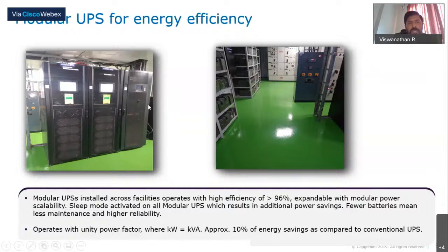Likewise, we have gone for a modular design so that we do not waste space. At the same time, these UPS are highly energy efficient and we could save 10% of the energy compared to a conventional UPS. This UPS gives almost 96% efficiency, and during the nights as well as weekends or holidays, when the UPS is not in use, these modules go into sleep mode, so they do not consume any power. And the next day, when the operation starts, the sleep mode modules wake up automatically and power the loads.